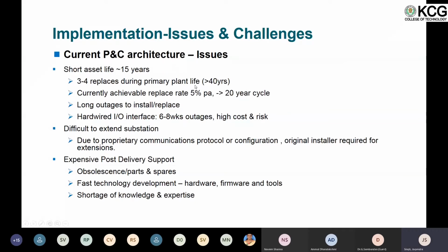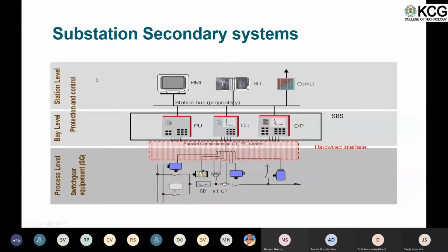All these electronic IEDs have a life of 15 to 20 years maximum. But a substation's life is more than 40 years. So all electronic devices will not survive for the whole life of the substation. So if you want to change one protection device, let us say you want to replace this device, you have to isolate it for safety reasons, and you need to take a shutdown, then only you can change it.